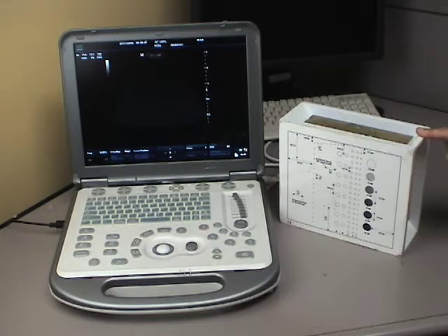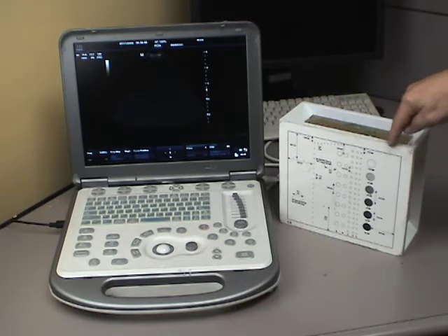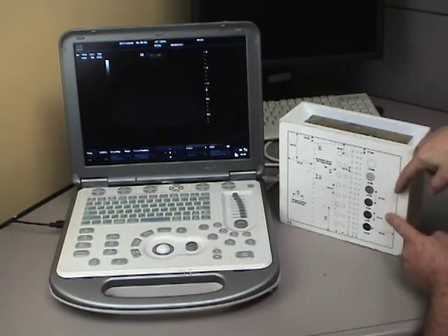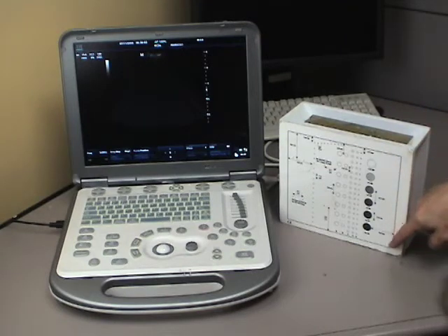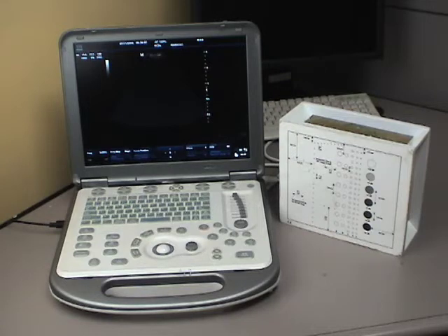All phantom has to have the same amount of attenuation as the body, meaning as the ultrasound signal goes in, it's attenuated and it loses signal. It goes down and bounces back up again, and it has to lose that signal at roughly the same rate as it does in the body.